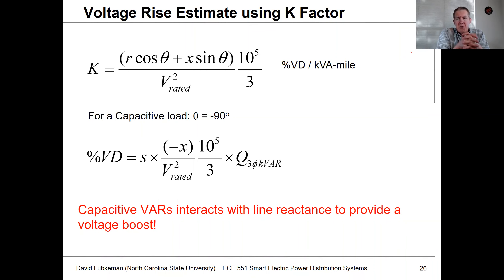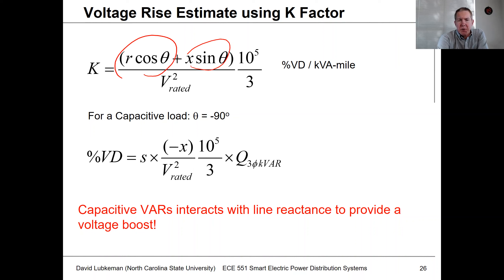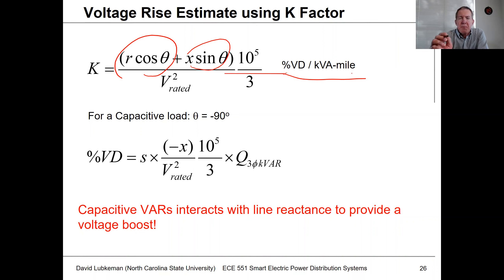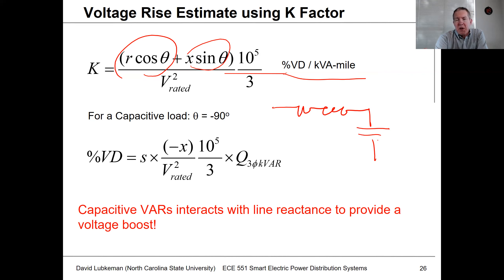Now let's take a look at how we can compute the voltage rise using the k-factor approach. As you recall, the k-factor had two different parts to it — a real part due to resistance and a reactive part due to reactance. It's a function of the power factor angle, in units of percent voltage drop per kVA mile. If I had a load on this line segment that was capacitive in nature, it would look from the sake of voltage drop calculations like a load with a power factor angle of minus 90 degrees.